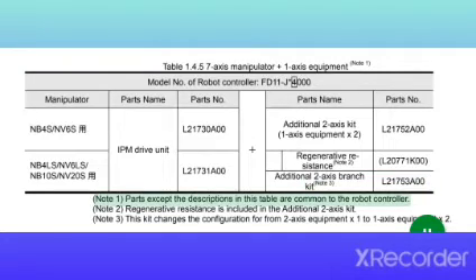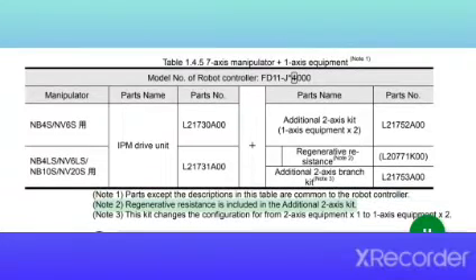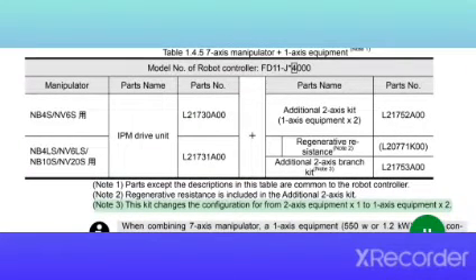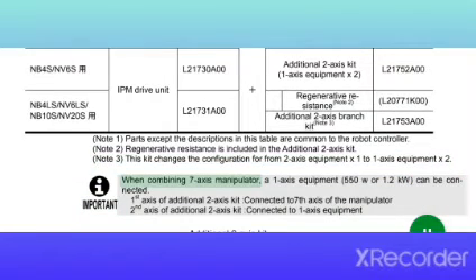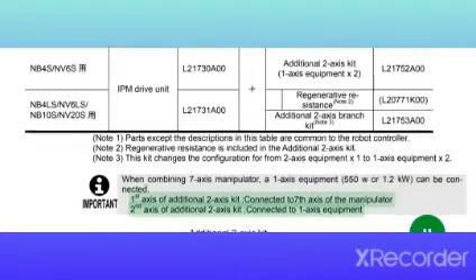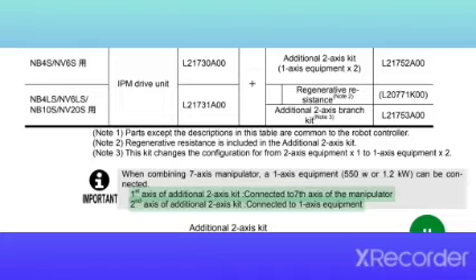L21753A00. Note 1. Parts except the descriptions in this table are common to the robot controller. Note 2. Regenerative resistance is included in the additional 2-axis kit. Note 3. This kit changes the configuration from 2-axis equipment X1 to 1-axis equipment X2. Important: when combining a 7-axis manipulator, a 1-axis equipment of 550W or 1.2 kilowatt can be connected. First axis of additional 2-axis kit connected to 7th axis of the manipulator. Second axis of additional 2-axis kit connected to 1-axis equipment.